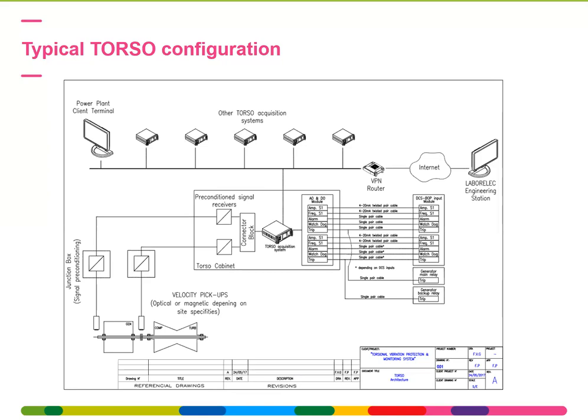The outputs towards the DCS can be configured quite flexibly. Typically, you have analog outputs showing the amplitudes at different frequencies of interest. You have alarm, watchdog, trip, digital outputs, all redundant, of course, to ensure the robustness of the system. Remote follow-up is possible in the commissioning phase, and also the possibility for the power plant to have a client terminal to do any analysis of their own, just for transparency reasons.